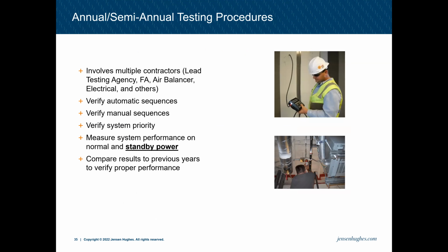With this, the annual testing usually involves multiple contractors. That's going to be a lead testing agency, someone who is knowledgeable of the smoke control systems and how they work. Then the fire alarm contractor usually, because the smoke control systems are controlled and monitored generally by fire alarm systems. I'm sorry, when I said fire alarm contractor, I meant an ITM firm. Sometimes contractors and installers also have an inspection, testing and maintenance group. Other times they don't. So that's generally the fire alarm ITM for the building, the firm that does the building's quarterly or annual tests.